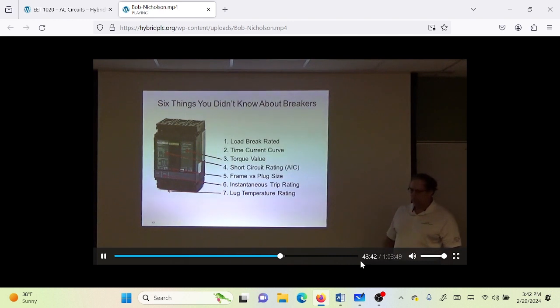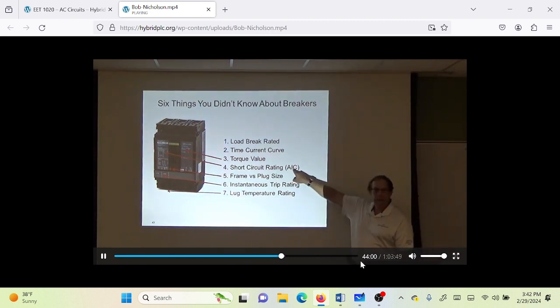Short circuit rating. Now, here's the beginning of your understanding about what short circuit rating is. If this is a breaker, and downstream is where this is feeding, that's where the arc flash is going to be. Now, you know fault current is going to come in the building, right? The fault current is going to go through this breaker. This breaker has to have an amp interrupting capacity that is equal to the fault current that's going to go through it.